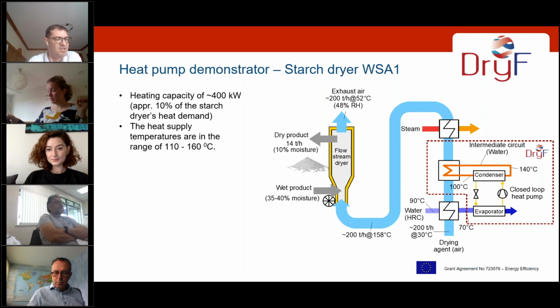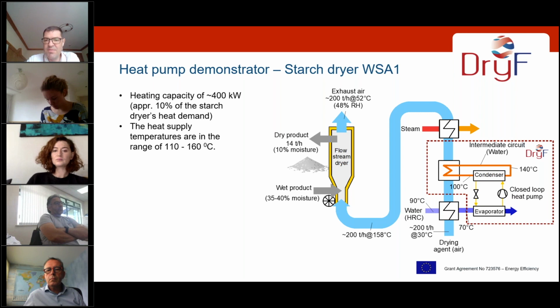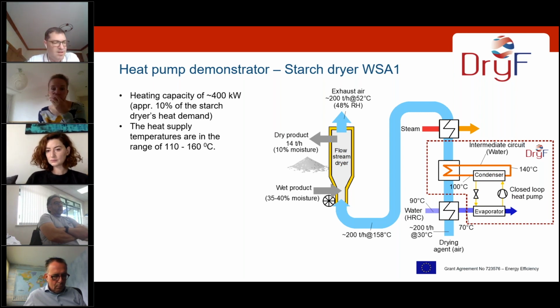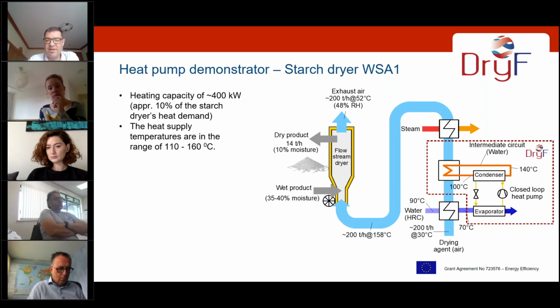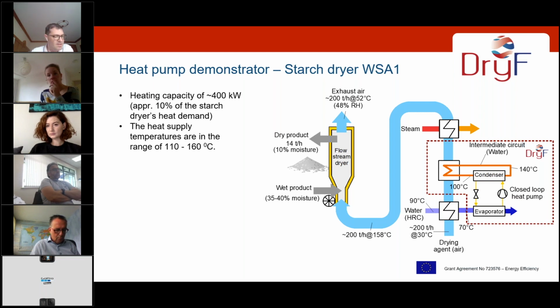And to increase the share of renewable energy, a novel closed-loop heat pump system was integrated in the starch dryer WSA1. As you can see here on the screen, the scheme of the starch dryer and the heat exchanger. The heat pump demonstrator has a heating capacity of approximately 400 kilowatts, which is something around 10% of the total wheat starch dryer heat demand. It's integrated downstream of a water-to-air heat exchanger coming from our internal heat recovery cycle, and following this heat exchanger, this water, which has approximately 70 degrees Celsius, is used as a source for the evaporator of the heat pump.